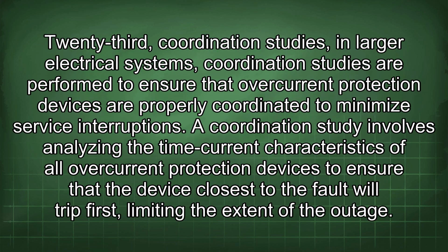23rd, coordination studies. In larger electrical systems, coordination studies are performed to ensure that overcurrent protection devices are properly coordinated to minimize service interruptions. A coordination study involves analyzing the time current characteristics of all overcurrent protection devices to ensure that the device closest to the fault will trip first, limiting the extent of the outage.